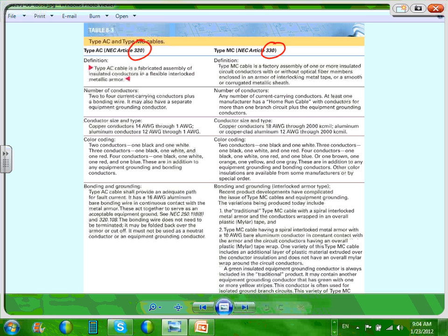The grounding conductor is fully insulated. So that's a major thing. Number of conductors: basically, everything is superior, guys. For number of conductors, you can get a lot of conductors in MC cable versus a very limited amount of conductors in an AC cable. Sizes, this is my favorite. Sizes, guys, look at the sizes you can get in an AC cable: 14 through 1. Is number 1 AWG conductor a limitation of the cable? Yeah. But if you're using an MC cable, look at the limitation on an MC cable: 2000 kcmil, that's as high as you can get.